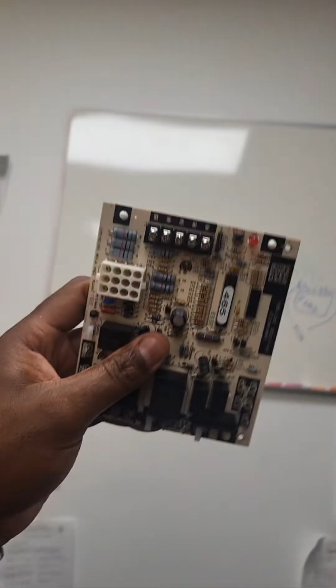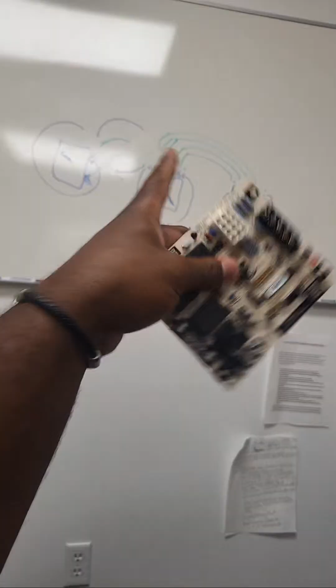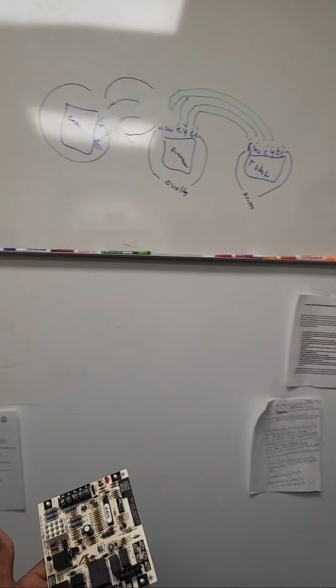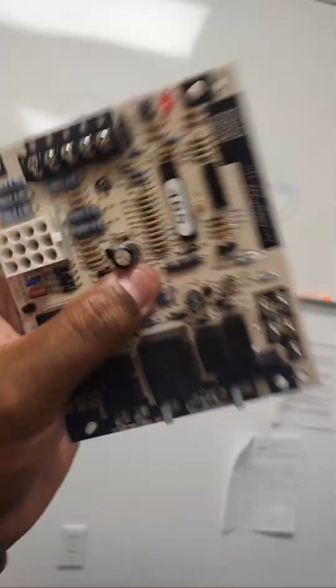With this low voltage troubleshooting, the more you see it, the more better you'll get at it. You've got to find a way based on what you're seeing to isolate the system. That's the best way of troubleshooting low voltage shorts, because my first time troubleshooting these, it wasn't broken down to me like that. I spent a bunch of time replacing fuses and hoping the fuse stayed lit, and that's really the wrong way of troubleshooting it.